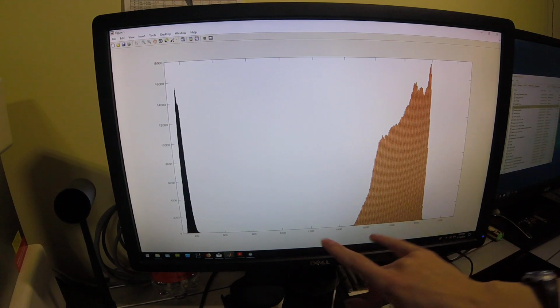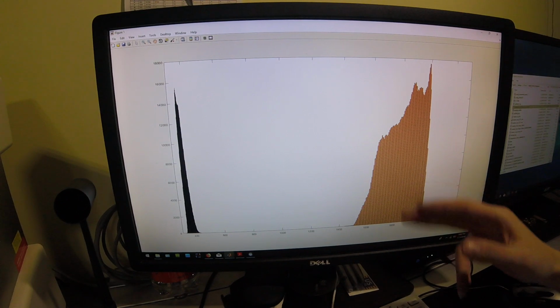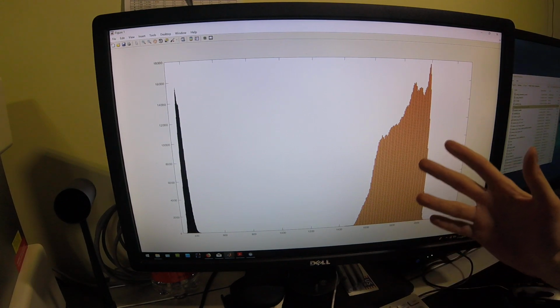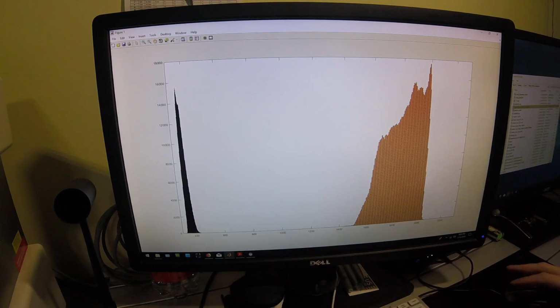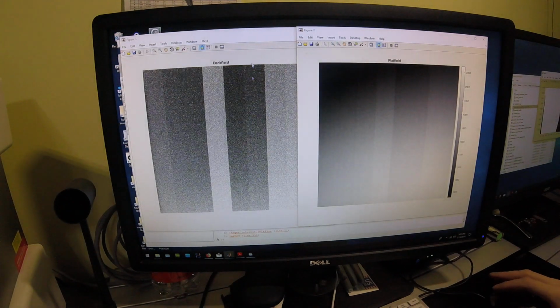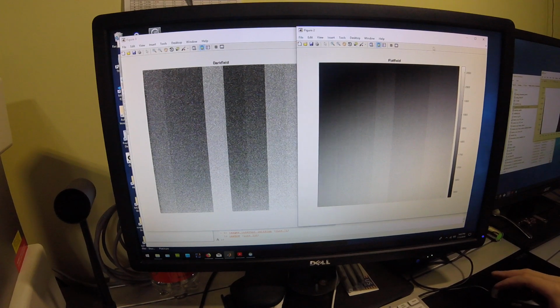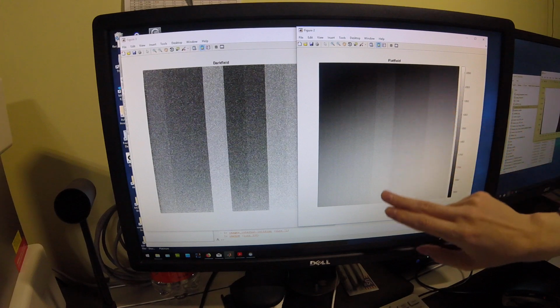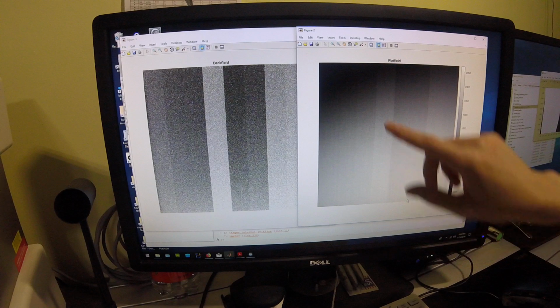So it's well below the maximum exposure that the detector panel can handle, but it still has sufficient power to generate images with very low noise after correction from the Flatfield and Darkfield. So the Darkfield image you've seen before, that's just variation in dark current on the CCD. The Flatfield image, on the other hand, you can see variations in sensitivity over the spatial area of the detector.